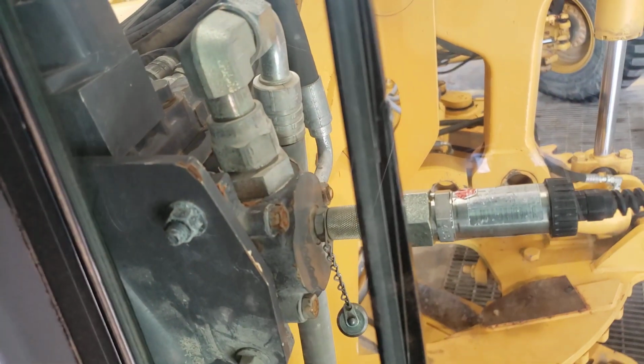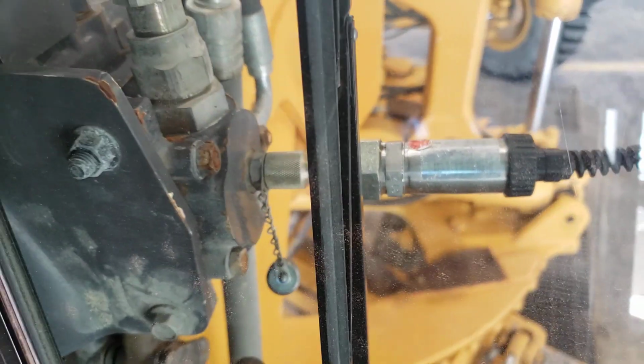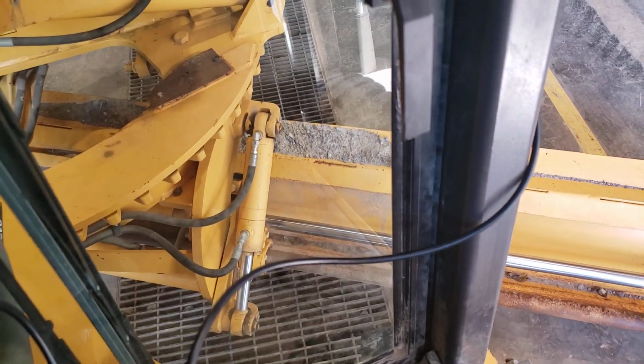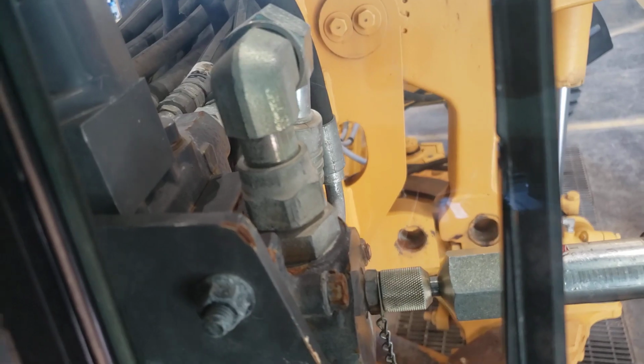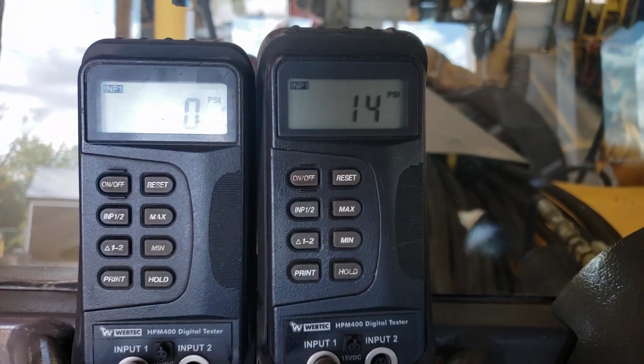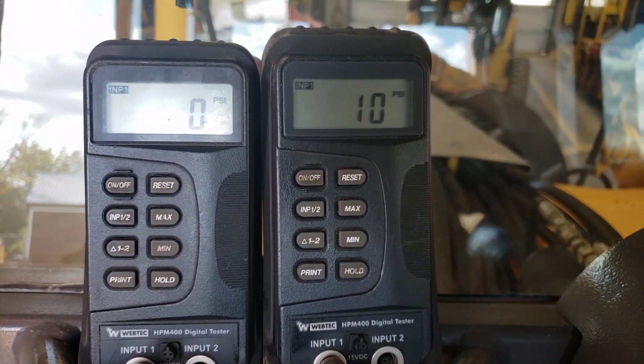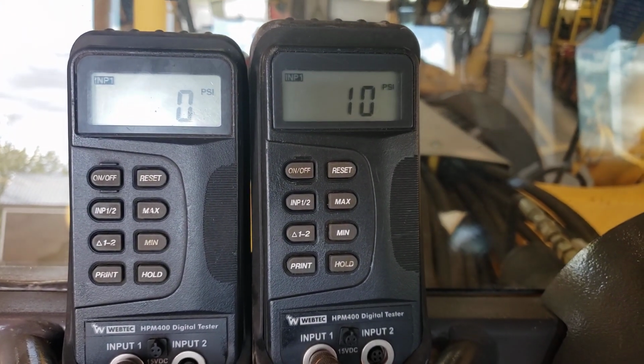So at the 10 bank valve at the front of the machine here, I've got a pressure transducer now hooked up to the hose feeding supply oil from the pump into the 10 bank valve. And I've got a gauge here just showing that pressure. Seems to be some residual pressure sitting in there that's now bleeding off because I just had the machine running.